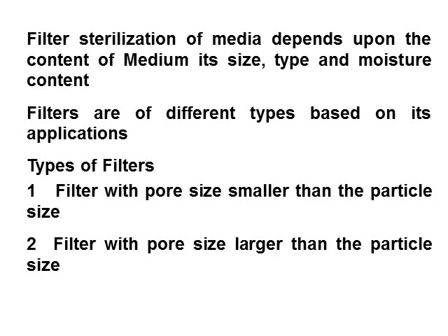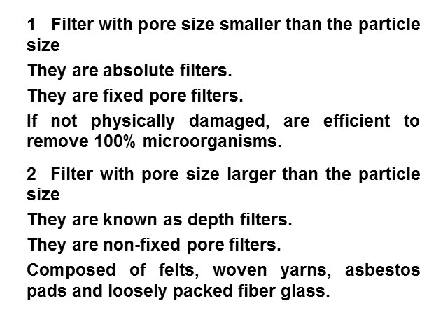Types of filters: The first type is filters with pore size smaller than the particle size. They are called absolute filters — fixed pore filters. If not physically damaged, they are efficient to remove 100% of microorganisms.